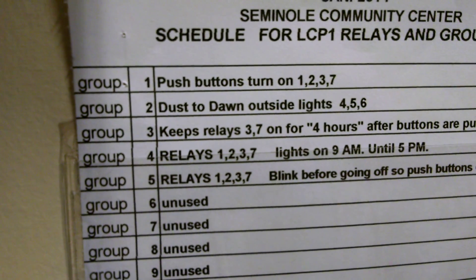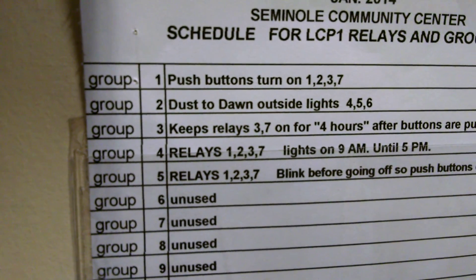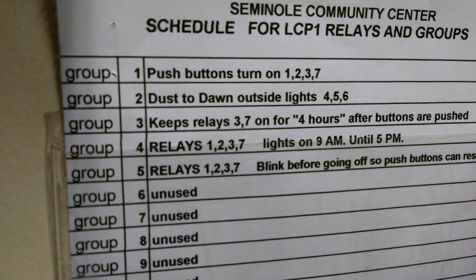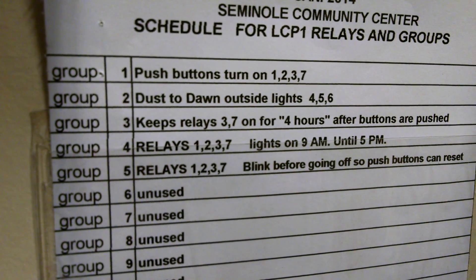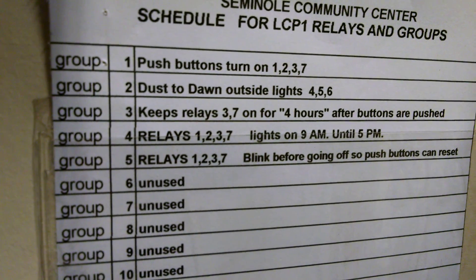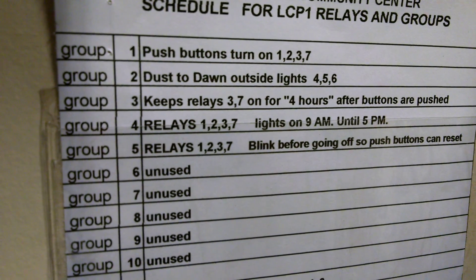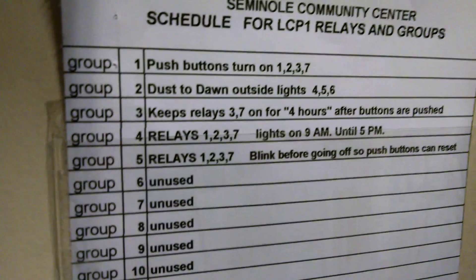Group number five states that relays one, two, three, and seven are going to blink before going off, so that you have time to go push the button to reset for another four hours. If you happen to be in here after five o'clock in the evening — even if you were in here at three o'clock in the morning — these lights are going to try to shut off and they're going to give you a warning with a couple blinks, to give you enough time to go over and hit the push button switch so you can give yourself another four hours.